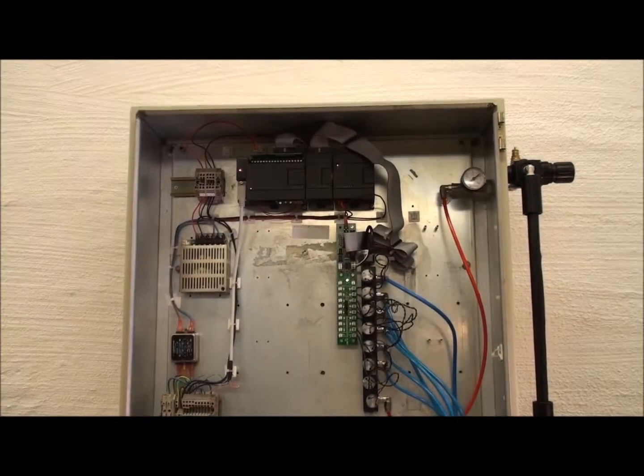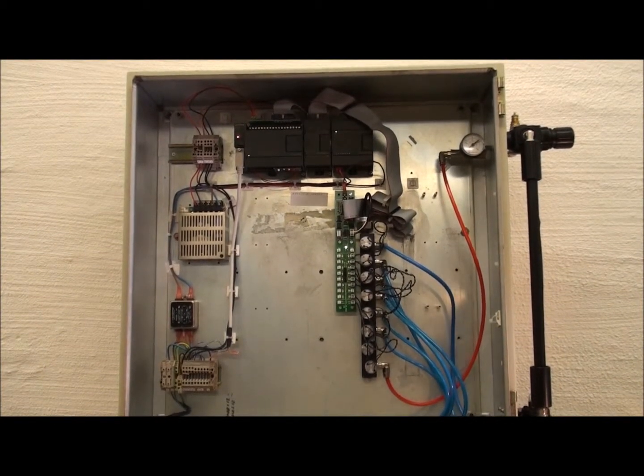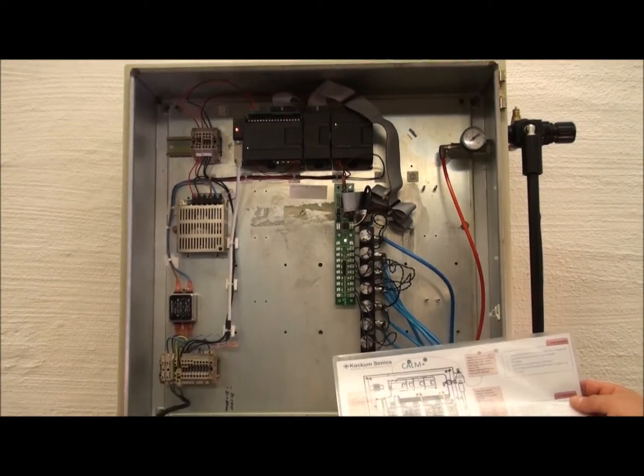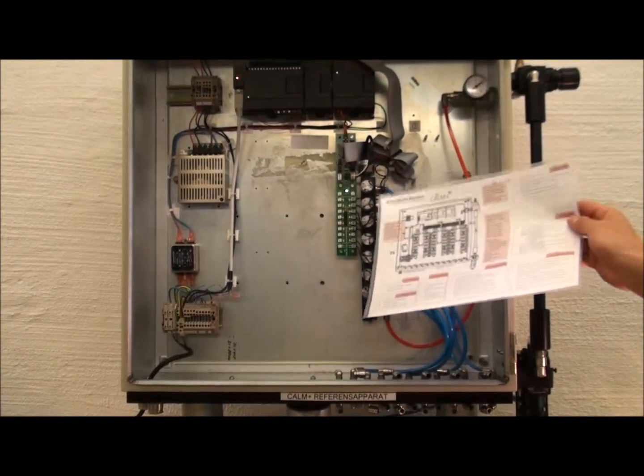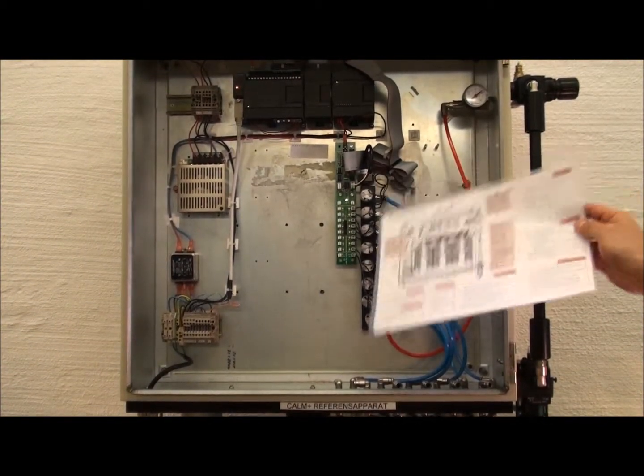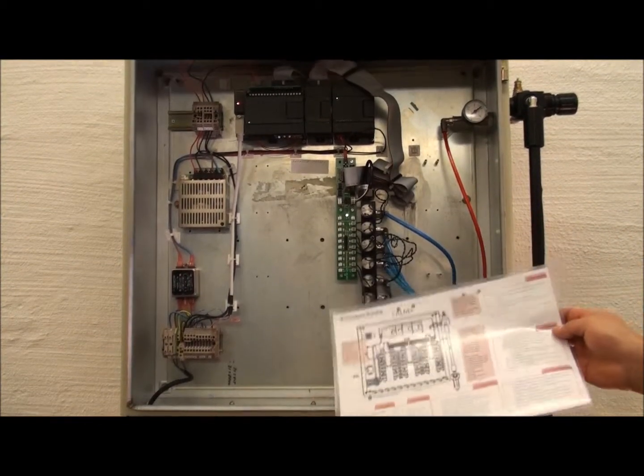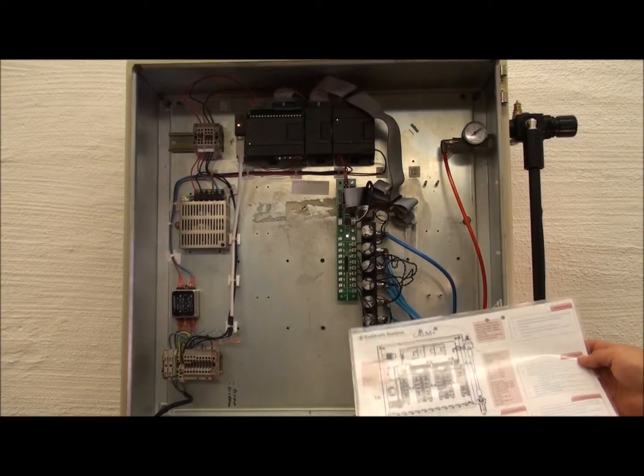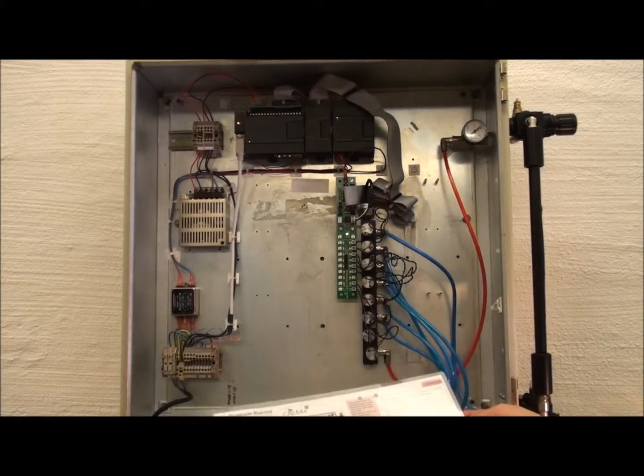So now we have tested pretty much everything in the system. We have tested two-way valves, we have tested the pressure sensor is working, we have tested the card is working, the PLC seems to be working. So there is just one thing to do, and it's to calibrate the system.